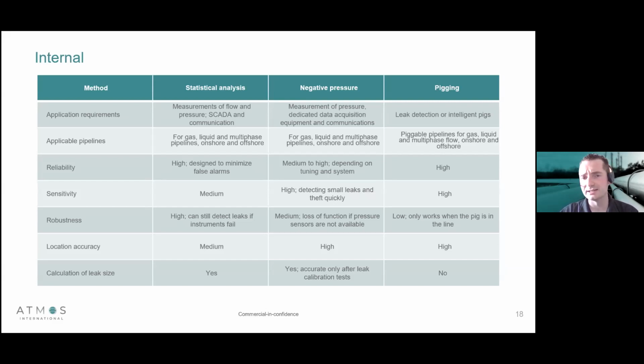In the 1980s, the negative pressure wave principle was developed in the US. This system is an onset detection method. So when a leak, theft, or rupture occurs, it generates a negative pressure wave that propagates along the pipeline in both directions. If you utilize pressure transmitters and RTUs to collect the data, you can provide a very accurate leak location. You can detect very quickly, and it can detect very, very small leaks. Now, the problem was when this was first developed in the 1980s, the internet and the infrastructure just weren't in place to deal with the high acquisition rate required. Generally speaking, most negative pressure-based systems collect at around 60 hertz. That's 60 samples a second.